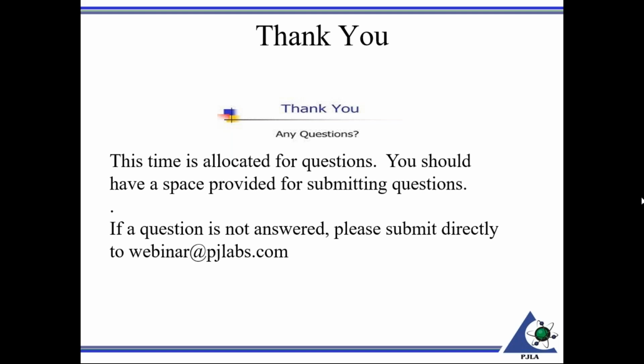Can I recommend a customer not to use a calibration equipment that was close to fail, or the decision is left to the customer? Let's take a look here a little bit, see exactly how that's worded. First of all, you have to be authorized to give that opinion. And if you look at the requirement under 7.8.7.2, I would think perhaps you might want to include that under 7.8.7.3, where you're going to do it by dialogue. It might be kind of hard to document there, but however, if you're basing it on the results obtained from the tested or calibration items, that should be clearly identified as such.